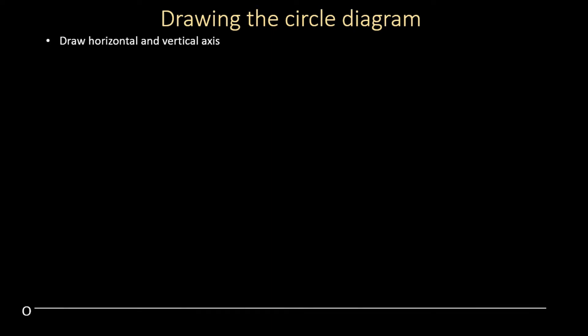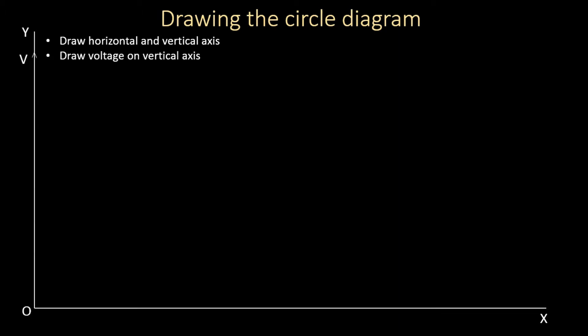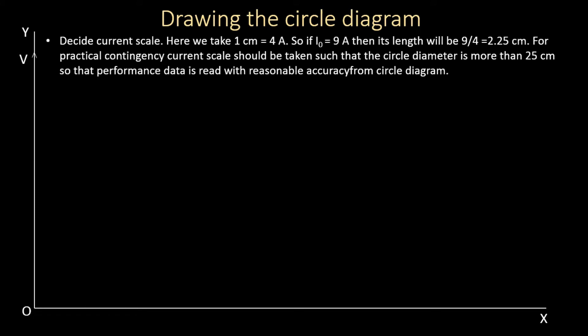We start by drawing horizontal and vertical axes with voltage on the vertical axis. For the current scale, 1 centimeter equals 4 amperes. Since no-load current is 9 amperes, the length will be 9 divided by 4, which is 2.25 centimeters. The current scale should be chosen such that the circle drawn has a diameter greater than 25 centimeters, so performance data can be read with reasonable accuracy.